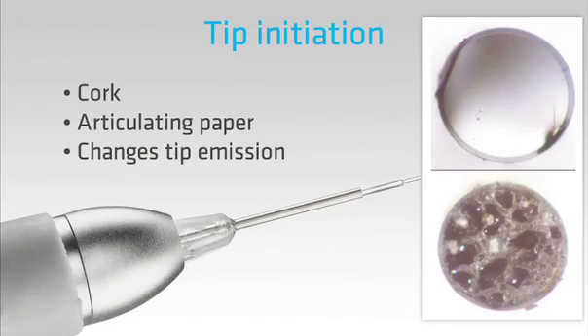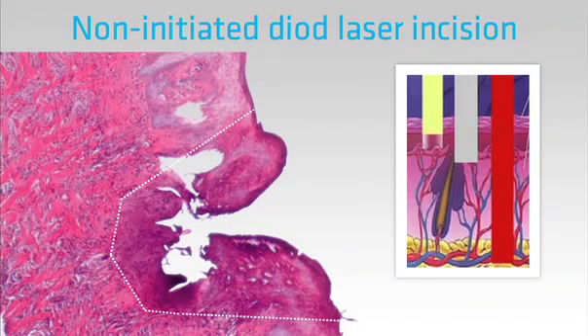Now let's return to the process of initiating the tip. We can do this by wiping the tip across a cork or over carbon articulating paper. The purpose of initiation is to change the pattern of energy emission — in simple terms, it constrains the laser energy in space. The material coated onto the end of the tip from the cork or carbon paper becomes very hot when the laser is used. We can use the same method to coat the side of the tip for doing an external bevel cut during a gingivectomy. If we don't initiate the tip, the laser energy will go further into the tissues and we will get more collateral damage. This histological slide of a laser cut sample of soft tissue shows this damage on the side of the incision.